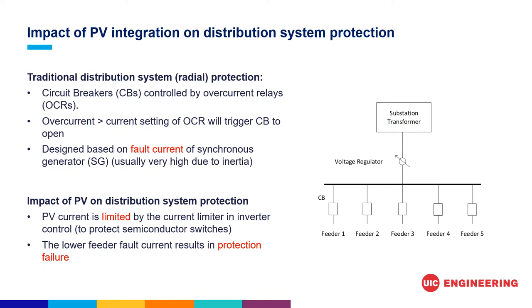In the diagram, we can see that the traditional radial distribution systems are protected by circuit breakers controlled with overcurrent relays. When an overcurrent measured by the relay exceeds the current setting, it will trigger the circuit breaker to open and isolate the fault. It is noted that these settings are designed based on the fault current of synchronous generators. These currents are usually very high due to the inertia of the synchronous generator and can be easily detected by the overcurrent relay.